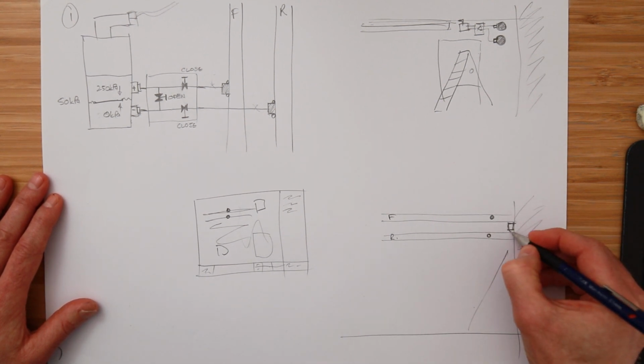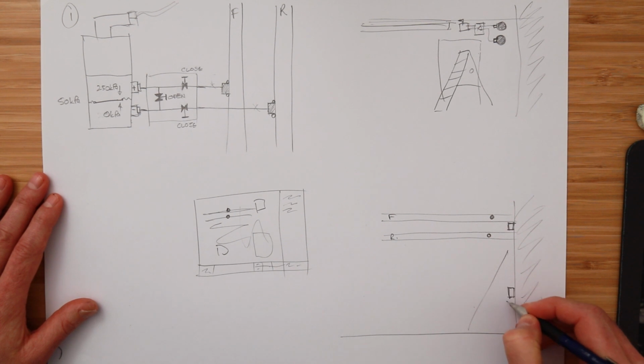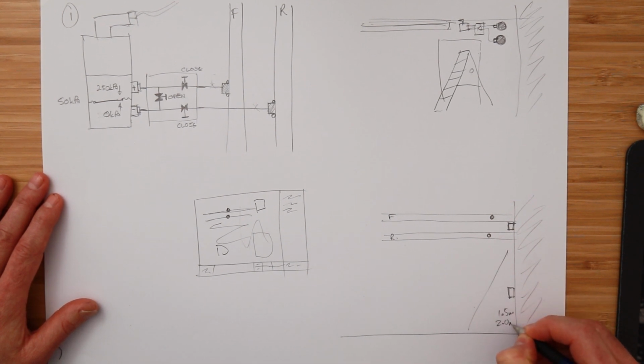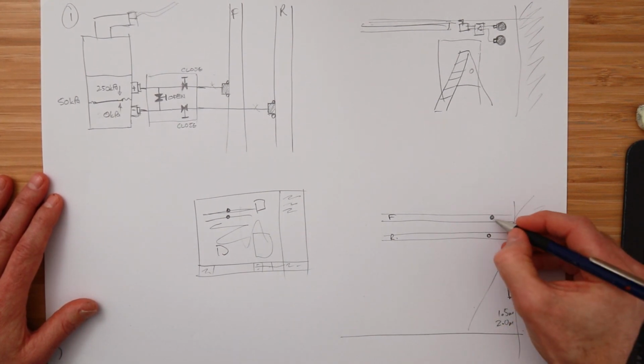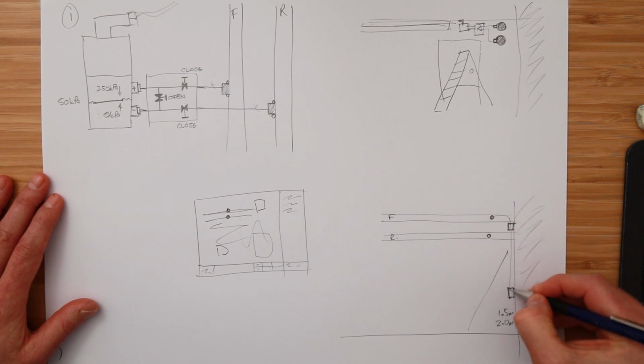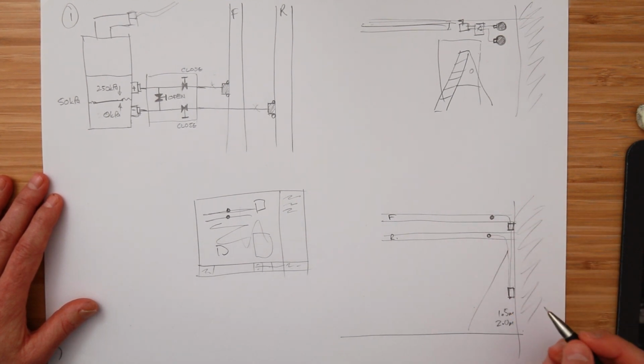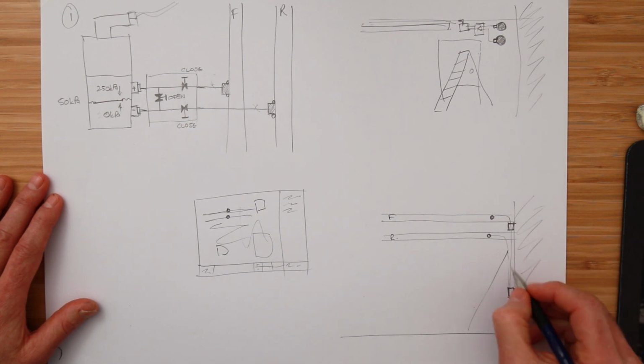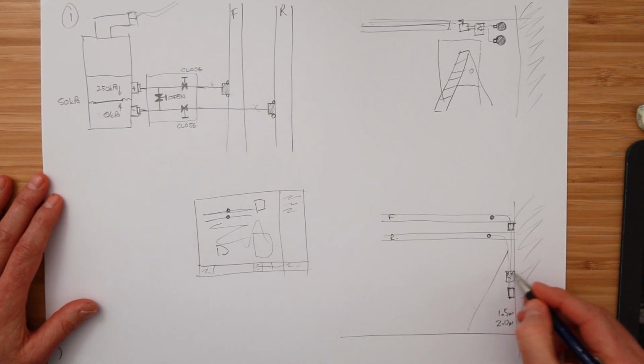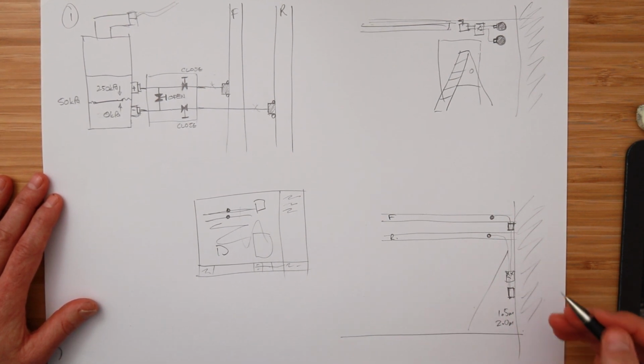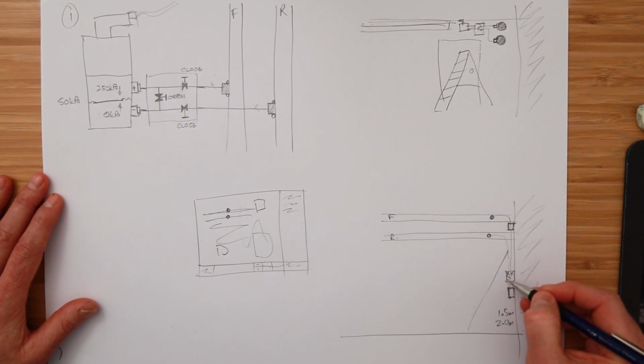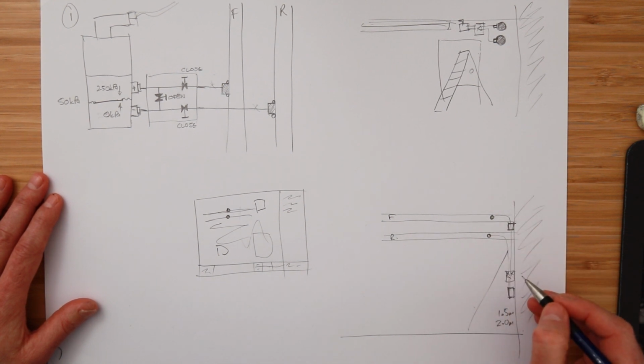So what we want is the transmitter to be installed here, 1.5 meters, or maybe 2 meters above ground at eye level. Now, mechanical will run the 6mm copper tubes down to here. If you told them to do that in your design phase, you told them, I need the manifold here with the 3 valves on, and I need this installed at a safe working height, 1.5 meters, they would probably do that. But if you don't tell them that, they won't do it.